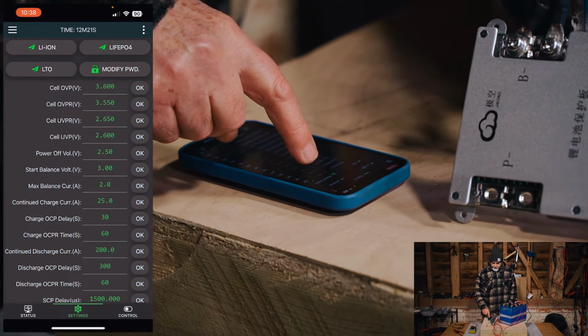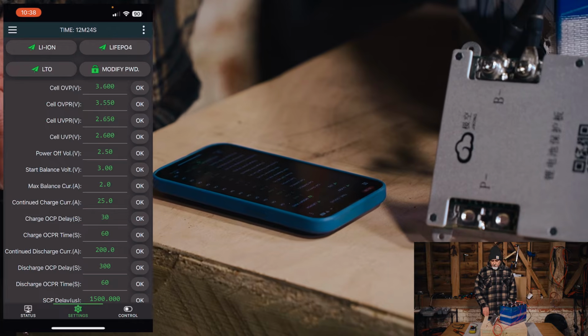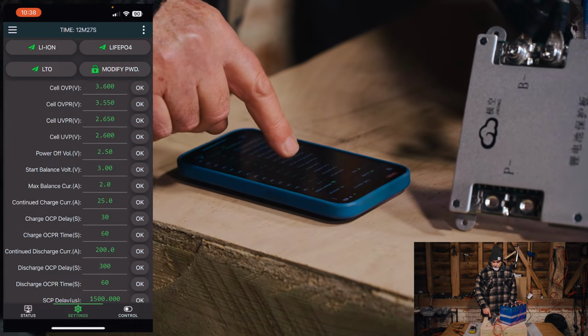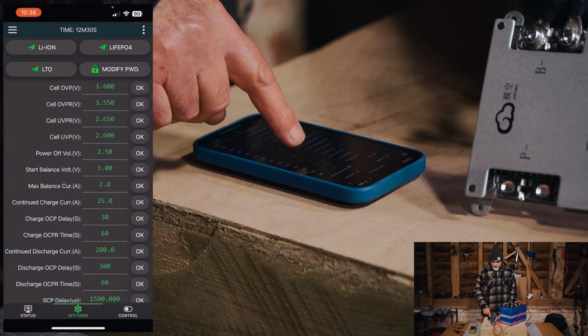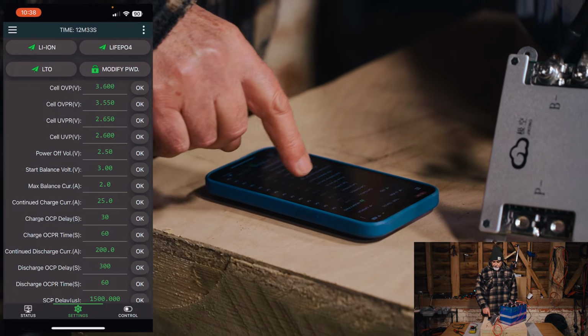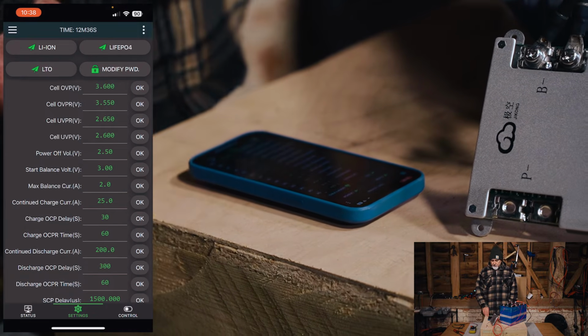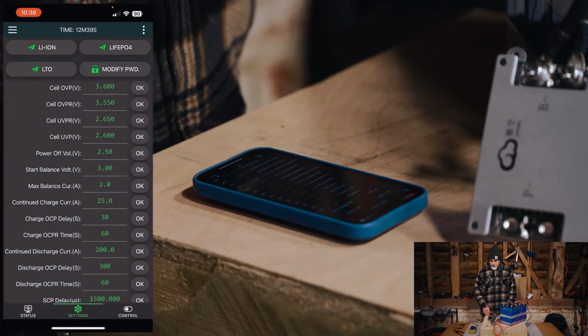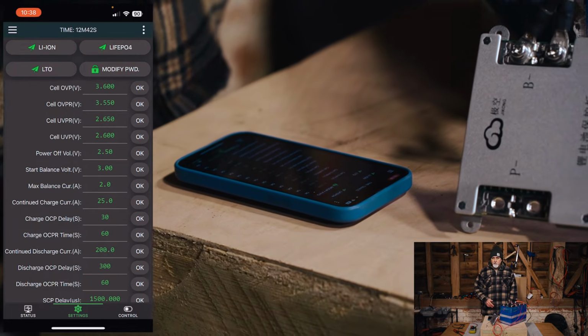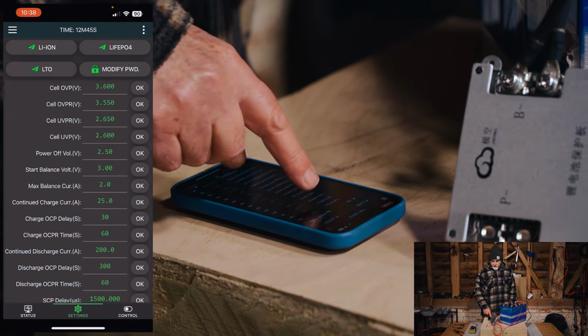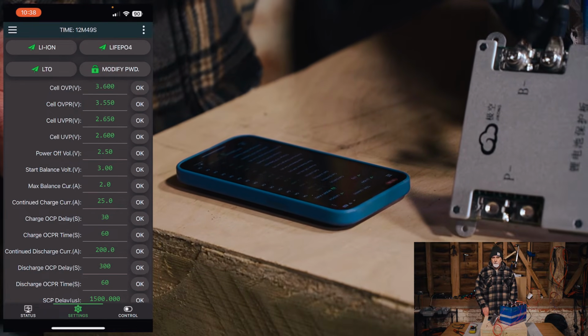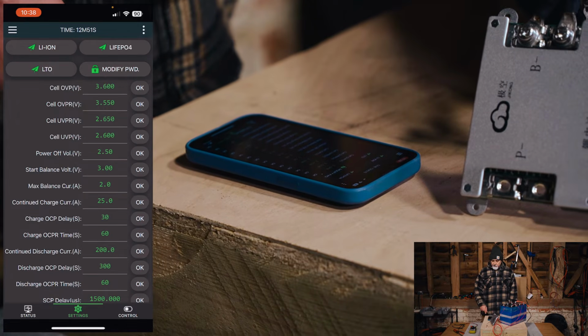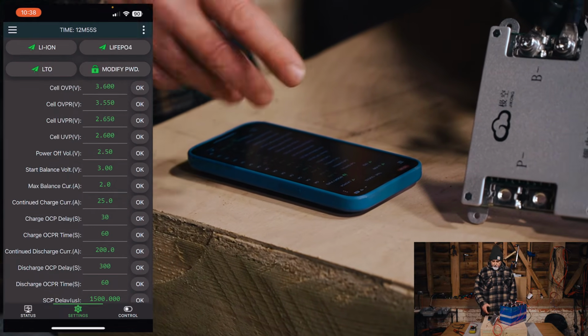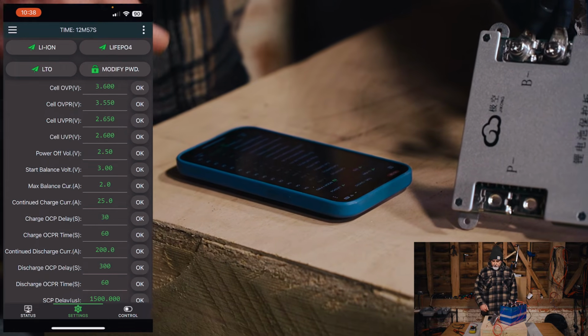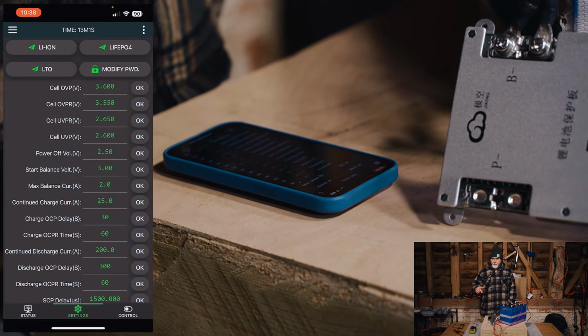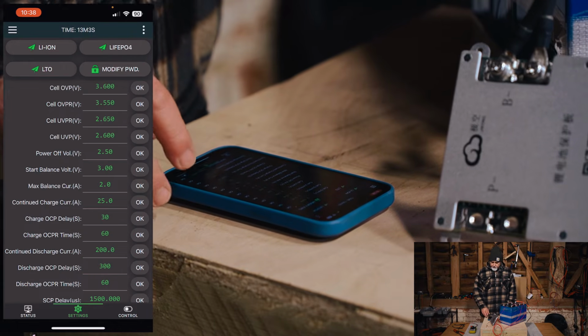You've got four parameters at the top here: your cell over voltage protection and its reset value, and the under voltage protection and its reset value. The reset values are in the middle. You may want to change these, but actually the defaults are fine. If you definitely want to charge at 14.6 volts, you'll need to change your cell over voltage protection to 3.65 to make up that 14.6 volts. But you can set these however you want. Those first four are to protect your cells from over voltage and under voltage, over voltage when charging, under voltage when discharging.